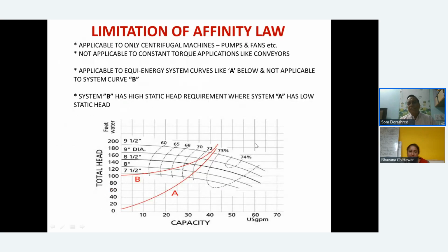But there are limitations in the affinity law. What is the limitation? It is applicable only to centrifugal machines. If you have a reciprocating machine, this is not applicable. For reciprocating machines, maybe it is just proportional to the power; it is not a cubic proportion. It is also not applicable to constant torque applications like conveyors, or where you have a very viscous fluid and need high torque, or where you have very high static pressures. It may not really be applicable.